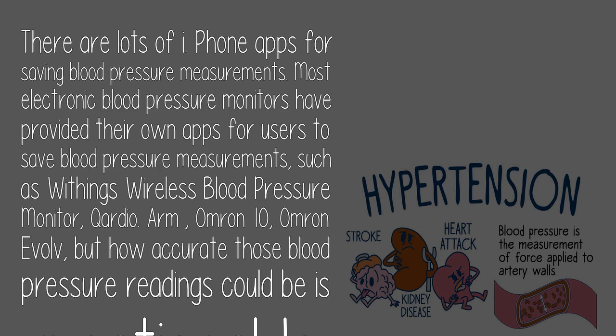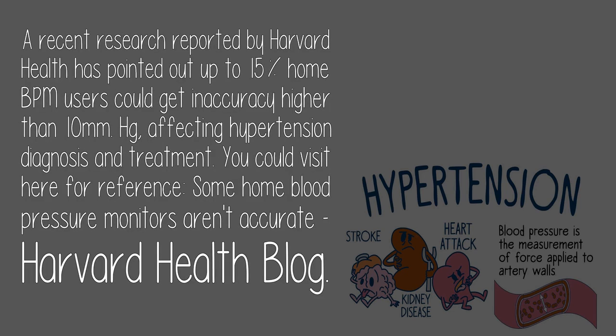But how accurate those blood pressure readings could be is questionable. A recent research reported by Harvard Health has pointed out that up to 15% of home blood pressure monitor users could get readings with an accuracy error higher than 10 millimeters Hg, affecting hypertension diagnosis and treatment.